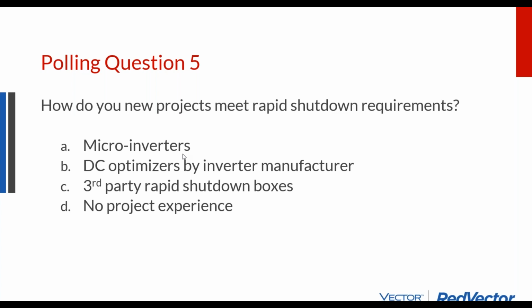So with microinverters and DC optimizers, they're nice because you get monitoring systems associated with every single panel on the roof. So you can see what every single solar panel on the roof is doing. As an installer, what I don't like is that the microinverters or DC optimizers are complicated. It's like putting a little computer behind every single panel up on an inaccessible place of the building that's subject to temperature extremes, critters, animals, rain, ice, so it's just a lot can go wrong up on the rooftop, and it's not in anybody's financial interest to make unnecessary maintenance trips up to the rooftop.